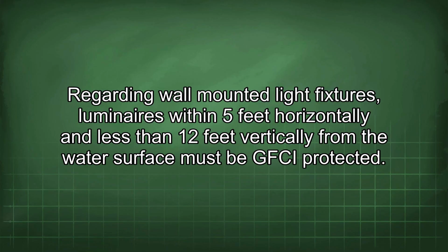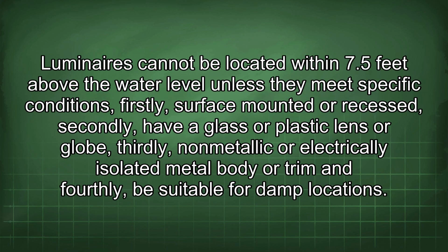Regarding wall-mounted light fixtures, luminaires within 5 feet horizontally and less than 12 feet vertically from the water surface must be GFCI protected. Luminaires cannot be located within 7.5 feet above the water level unless they meet specific conditions. Firstly, surface-mounted or recessed. Secondly, have a glass or plastic lens or globe. Thirdly, non-metallic or electrically isolated metal body or trim. And fourthly, be suitable for damp locations.